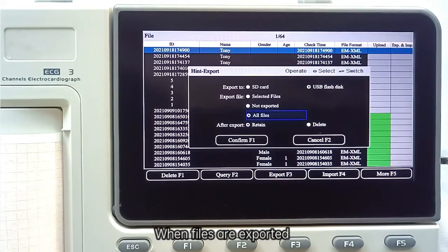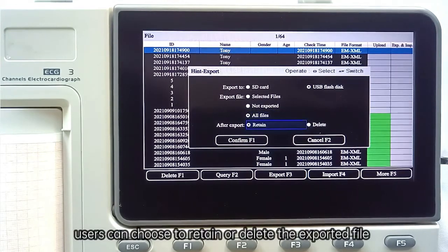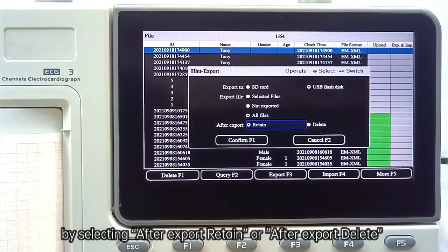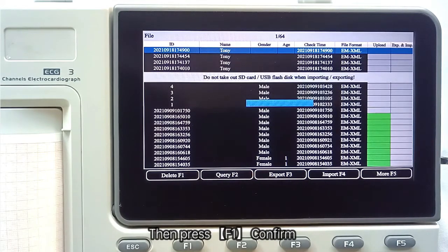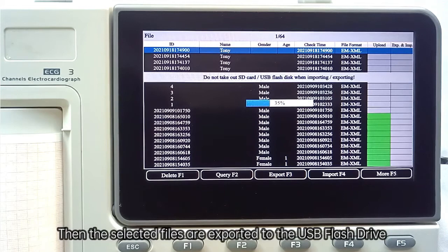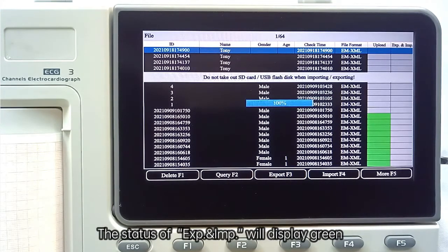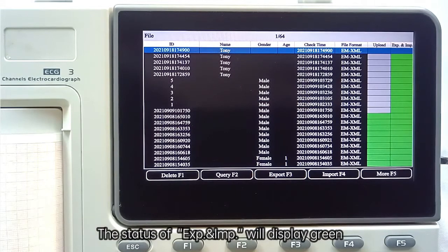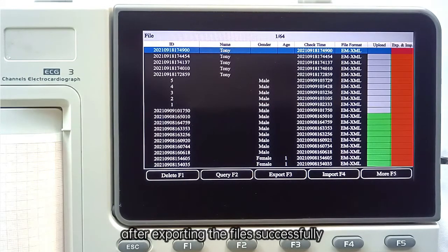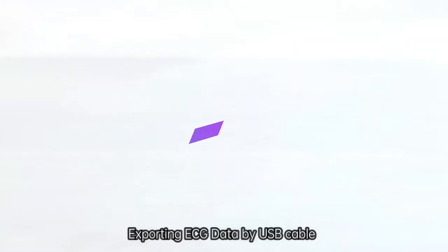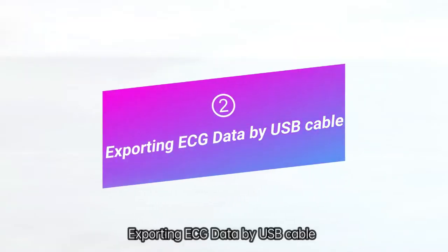When files are exported, the user can choose to retain or delete the exported files by selecting After Export Retain or After Export Delete. Then press F1 Confirm. Then the selected files are exported to the USB flash drive. The status of export and import will display green. After exporting the files successfully, we move on to exporting ECG data by USB cable.